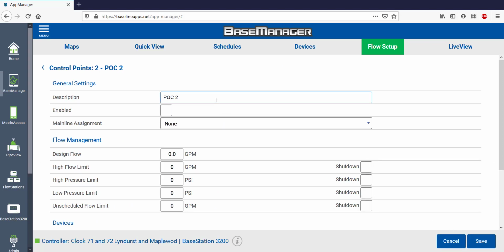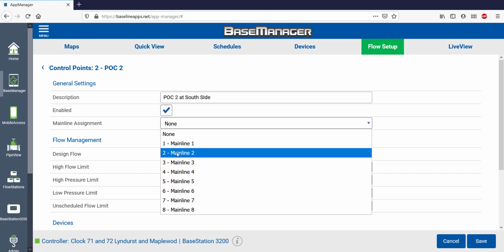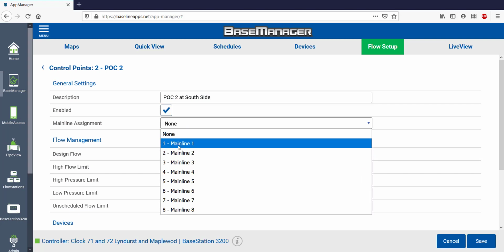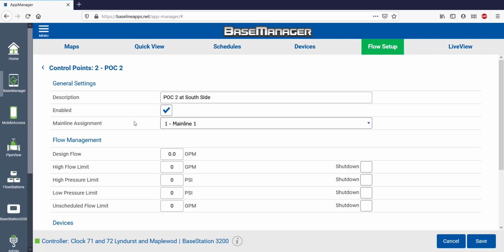On control point 2, I'll name it like I've been naming the others, then ensure it's enabled. This time I'm going to assign or associate control point 2 with my only mainline, which is mainline 1. Control point 2 is smaller, so it only has a design flow of 60 GPM. I'll set the high flow limit about 20% higher, or 75 GPM, and have it shut down if it exceeds that 75 GPM. I'll set the unscheduled flow to 20 GPM just like I did for control point 1.